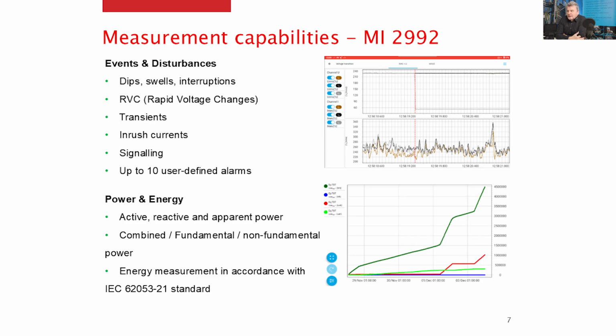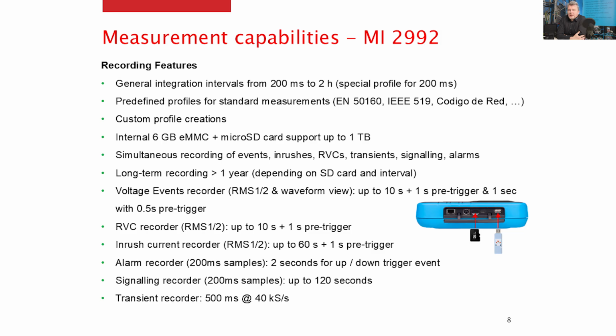And energy measurement is done in accordance with the IEC 62053/21 standard. A huge improvement was done in the recording features. So we are supporting integration intervals from 200 milliseconds up to 2 hours. For 200 milliseconds, we create a special profile where a specific register is defined, and the registration period is only 200 milliseconds. So what is included inside, you need to check in the user manual, where each of our defined profiles is explained with what is included and which integration periods are defined.